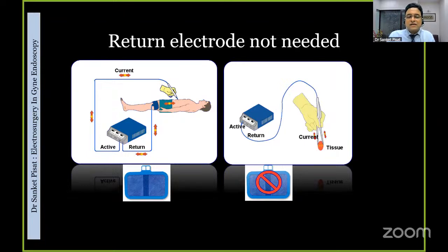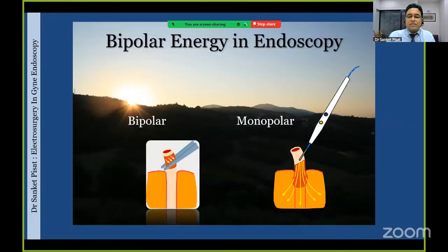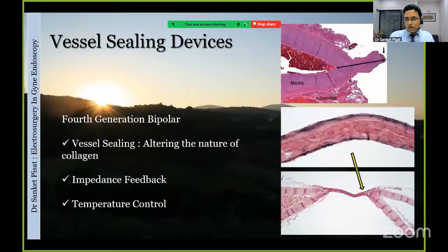Okay, so I hope that is very clear. You do not require it because the circuit is completed locally. It is not that the circuit is not completed. By principles of physics, it has to be completed, but it is completed locally within the arms of the instrument, and therefore there is no need for you to have a return electrode at all. So again, this is bipolar between two blades of the instrument, and that was monopolar, which I already talked about.